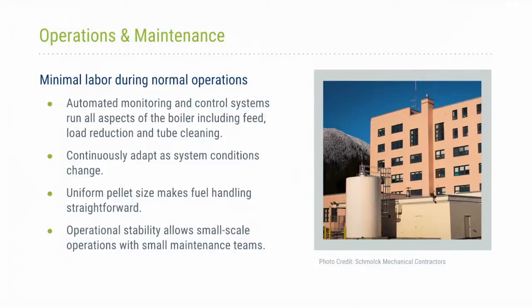Sometimes with chip boilers and other systems, you need to clean the boiler surfaces from ash and that kind of thing. This was actually an automated ash cleaning system where they could clean the tubes online, and that happened, I think, about every shift, every 8 hours or so. The system would shut off temporarily and it would clean itself. Ash removal is automated as well. So in essence, there's really nobody in the building to monitor the system for the most part, and the savings in operations and maintenance is really key. And because it's automated, it adapts to the system conditions and changing loads. It reacts fairly quickly. Solid fuels don't react to changes in loads quite as fast as a natural gas system or an oil system might, but with these pellet systems and this auger, it's pretty responsive. And again, it was a pretty stable system overall, and we'll get some more input from the people on the ground later in the presentation.